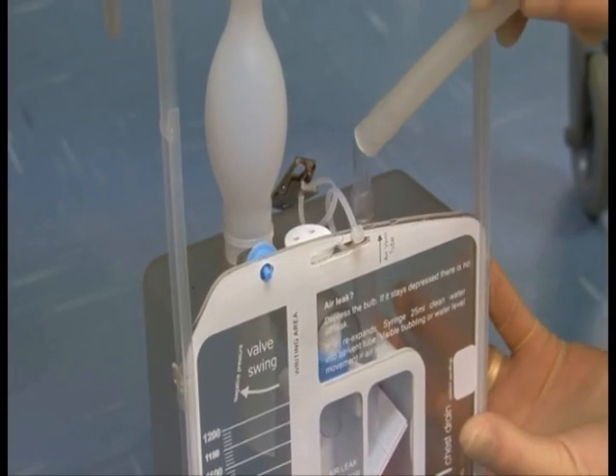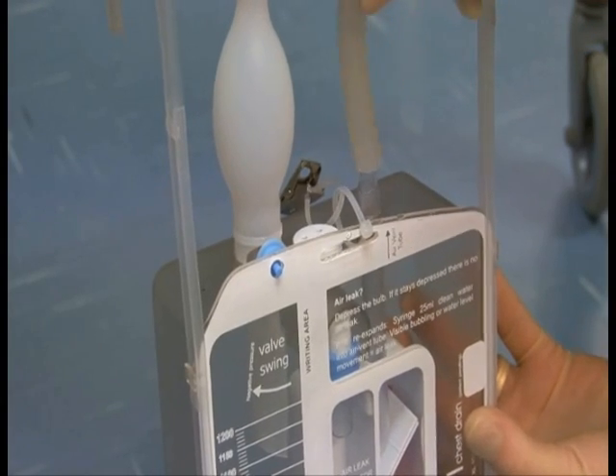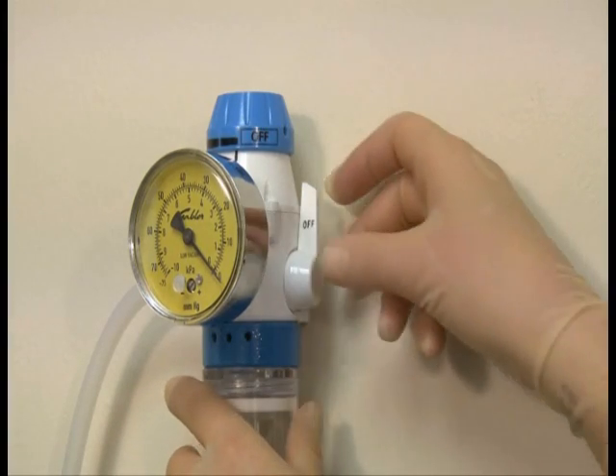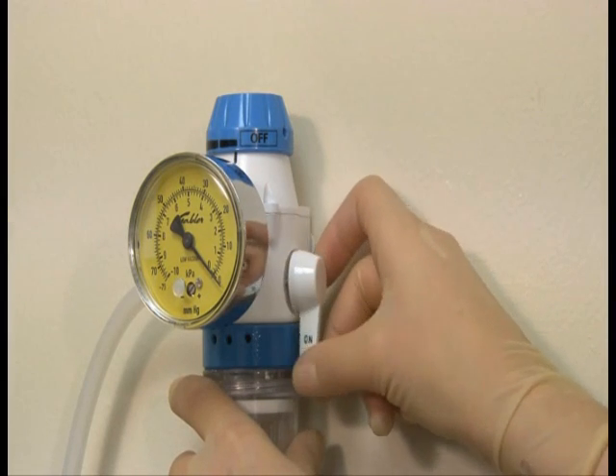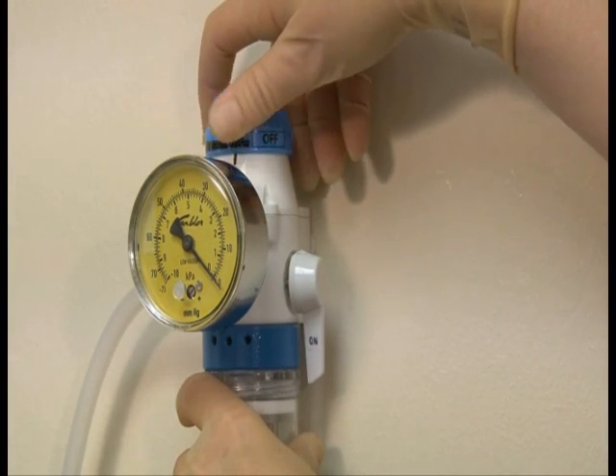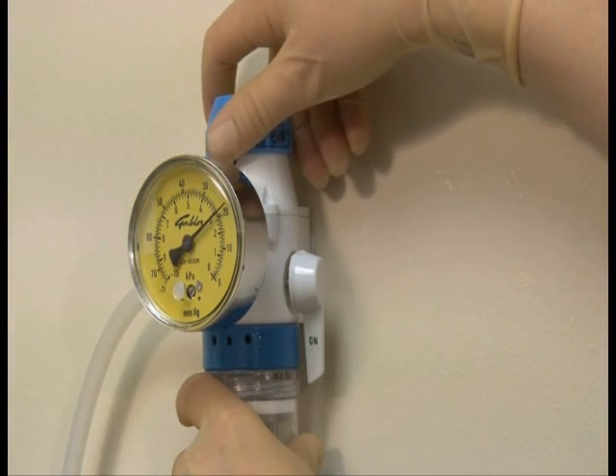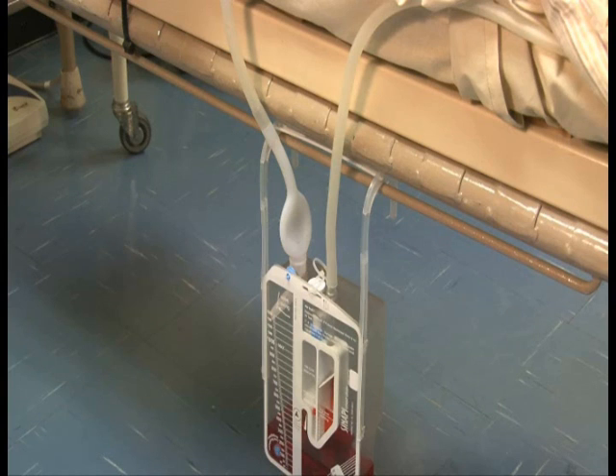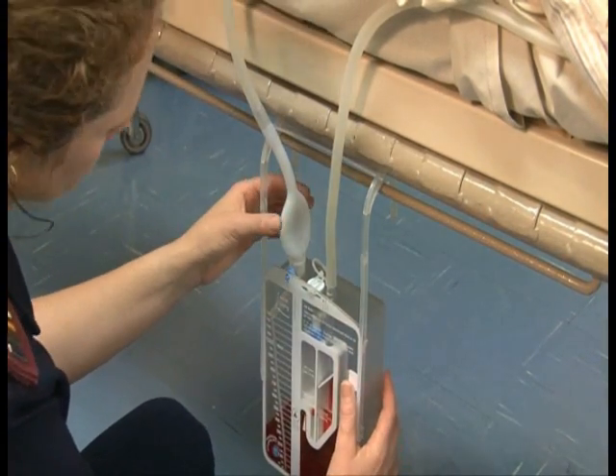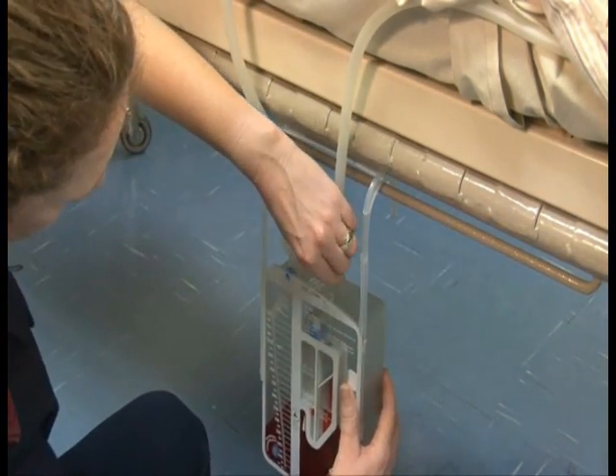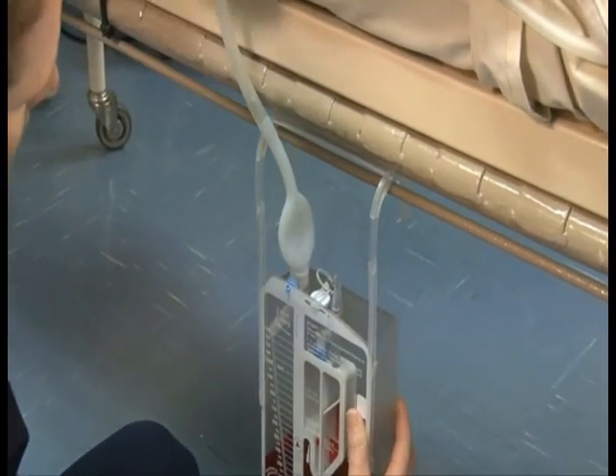When required, attach low pressure wall suction to the air vent tubing. The suggested suction pressure is between -20 and -40 centimeter water pressure or -2 to -4 kPa. The bulb will now stay depressed, indicating that suction is applied. If the bulb stays depressed when removing low pressure wall suction, negative pressure is maintained and wall suction can be removed.